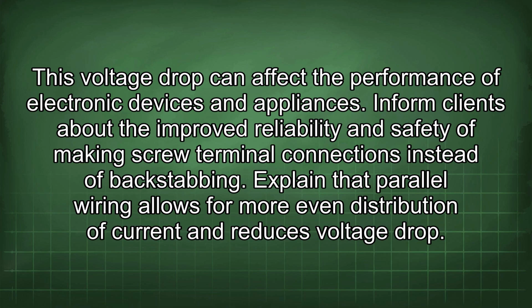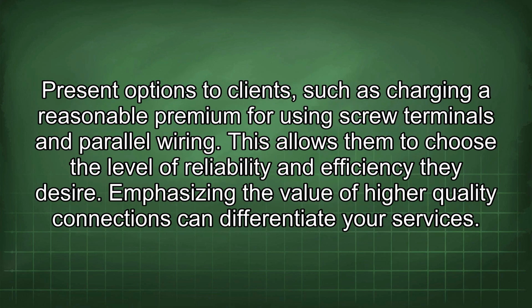Inform clients about the improved reliability and safety of making screw terminal connections instead of backstabbing. Explain that parallel wiring allows for more even distribution of current and reduces voltage drop. Present options to clients, such as charging a reasonable premium for using screw terminals and parallel wiring. This allows them to choose the level of reliability and efficiency they desire.